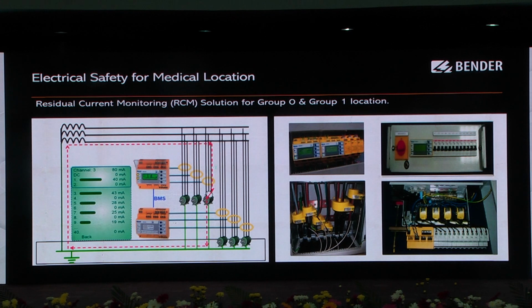You can see the type B CT. The type B CT needs a supply of plus and minus 12 volt. This is our special product. In the market, type B RCD is not available at the moment, and the lead time is almost around 25 weeks, maybe due to a raw material issue. But we already have the product, which we are already supplying to data centers and even thermal power plants, nuclear, chemical, and oil and gas, wherever it is mandatory. We regularly supply oil and gas in India, and for nuclear and thermal power plants type B CT is mandatory. So we have 12 channel and single channel.